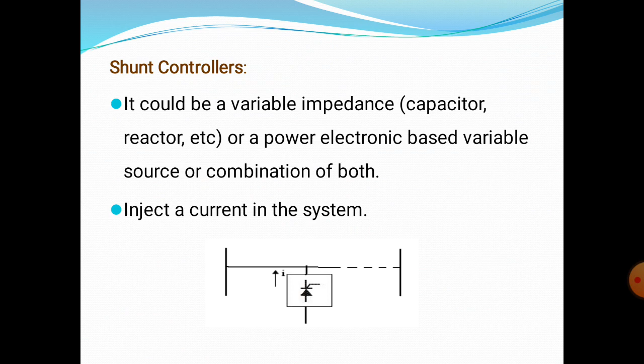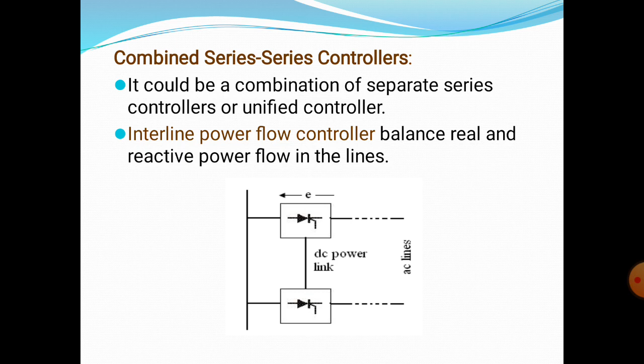And next one is combined series to series controllers. In this type, it would be a combination of separate series controllers, or unified controllers, which are controlled in a coordinated manner in a multi-line transmission system. In this diagram, the series controller provides independent series reactive compensation for each line, but also transfers real power among the lines via the power link. The real power transfer capability of the unified series to series controllers is referred to as interline power flow controllers. This is the main thing.